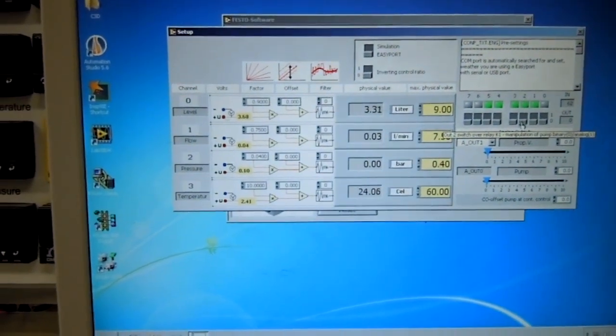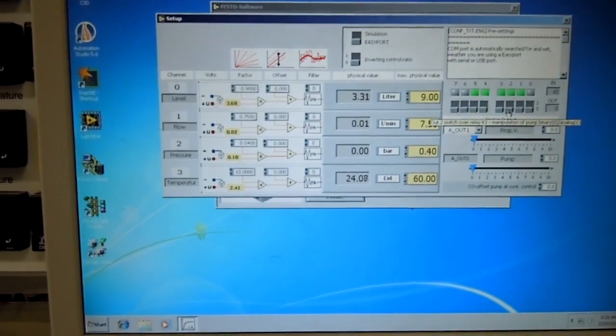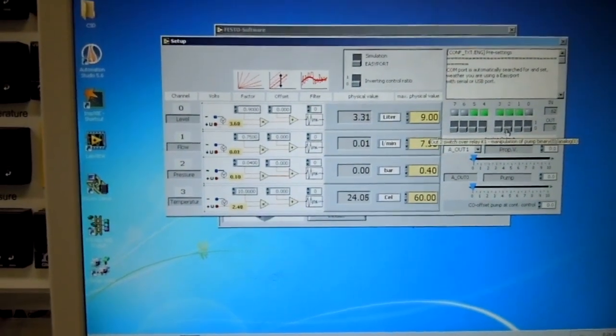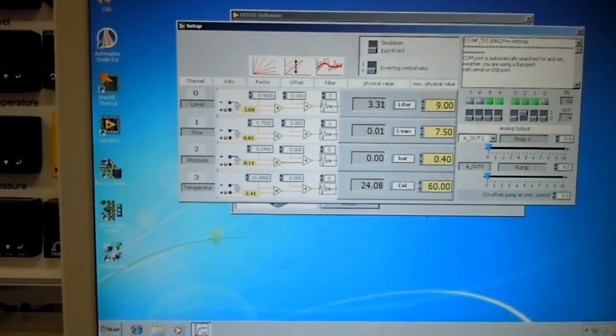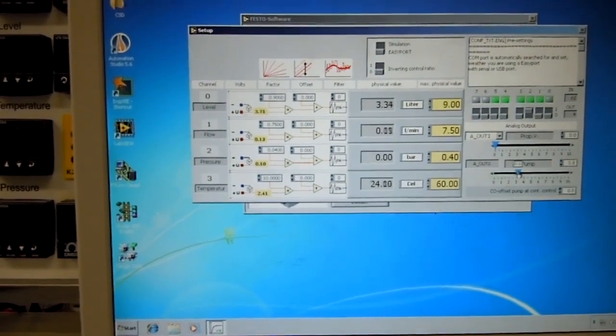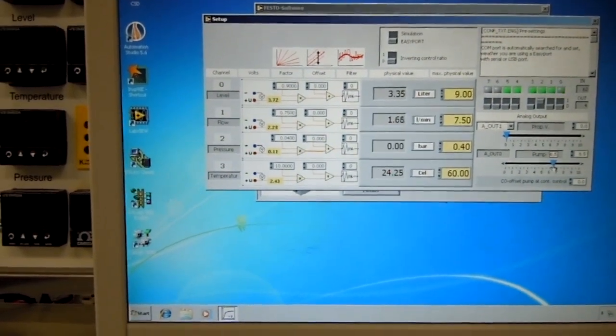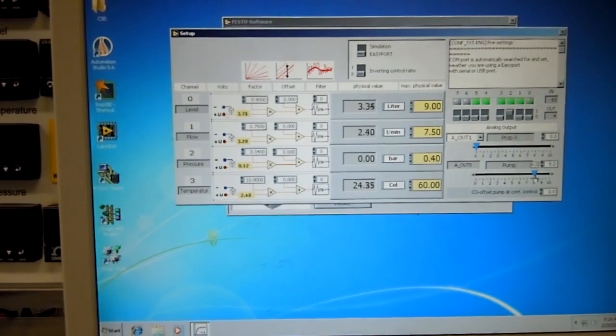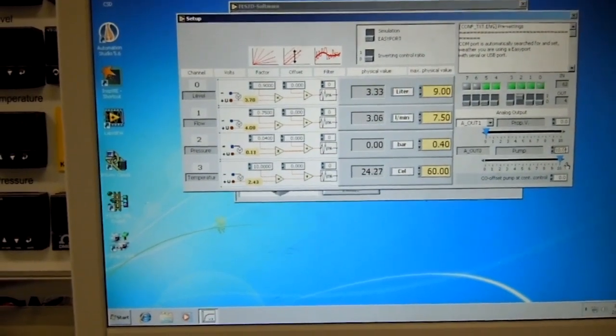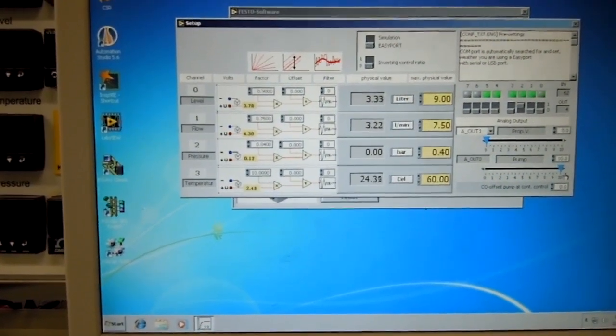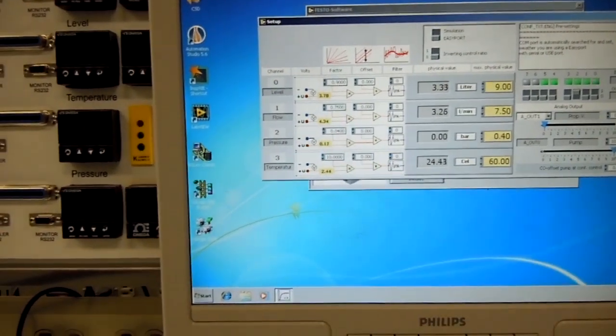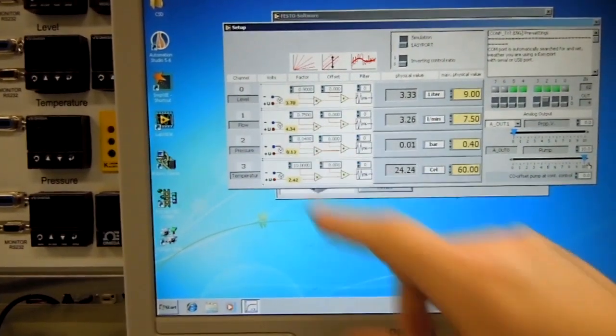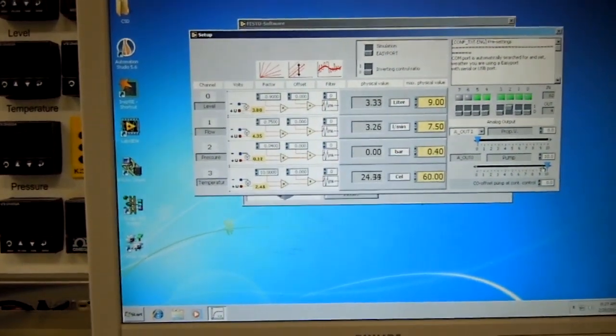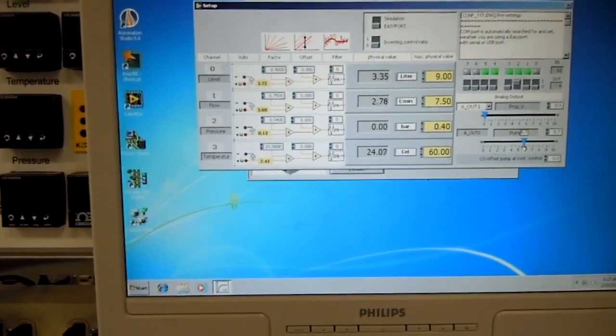There's a bit number 2, which controls whether the pump operates with an analog signal. So if I turn this on, now I can control the speed of the pump with an analog signal. So if I'm over here, I'm getting a lot higher speed, and you can see the flow rate changes as well. I'm getting 4.3 volts. And it's proportional, so I slow it down.